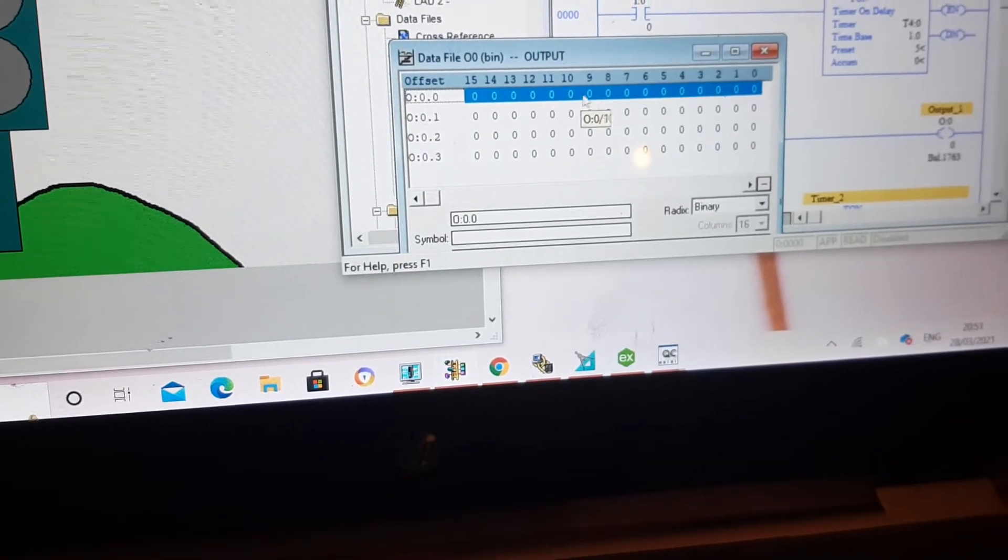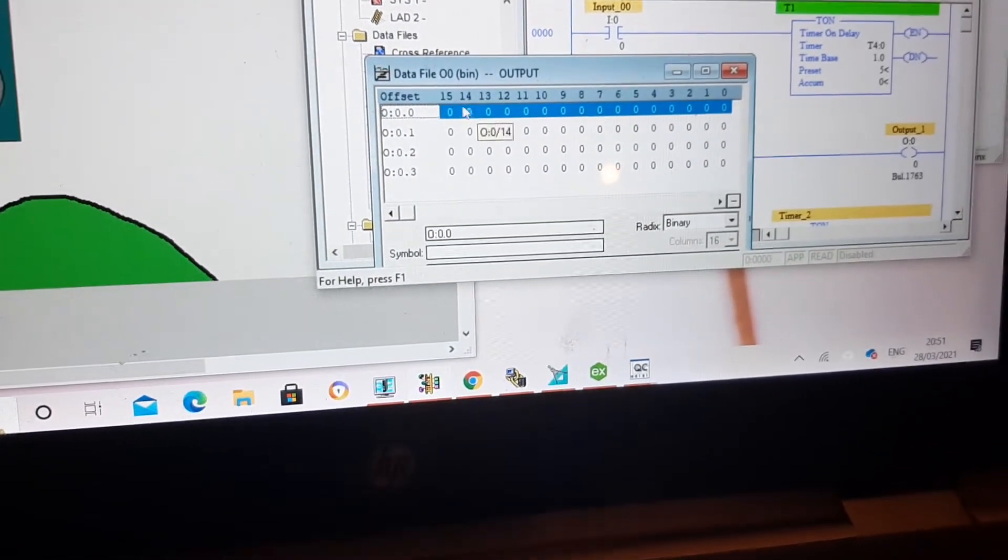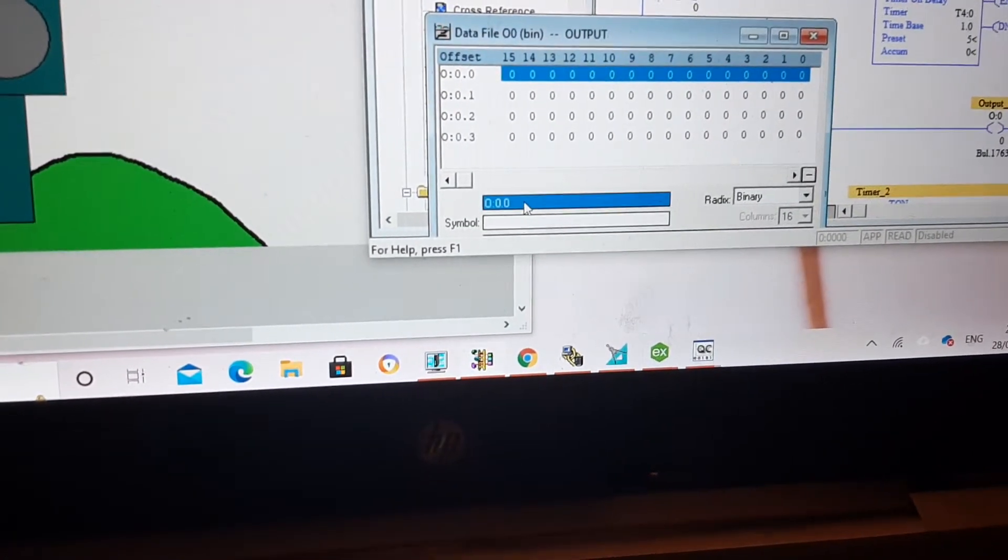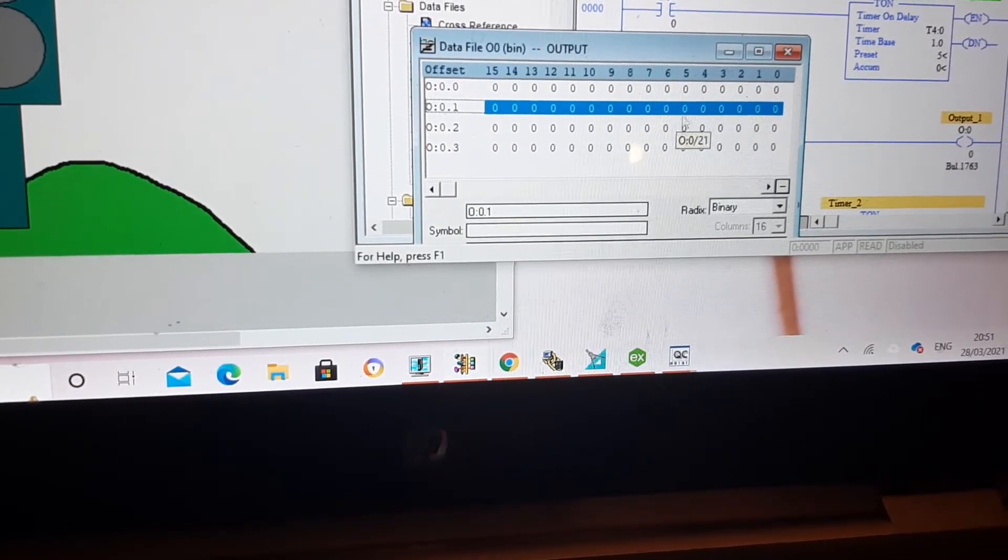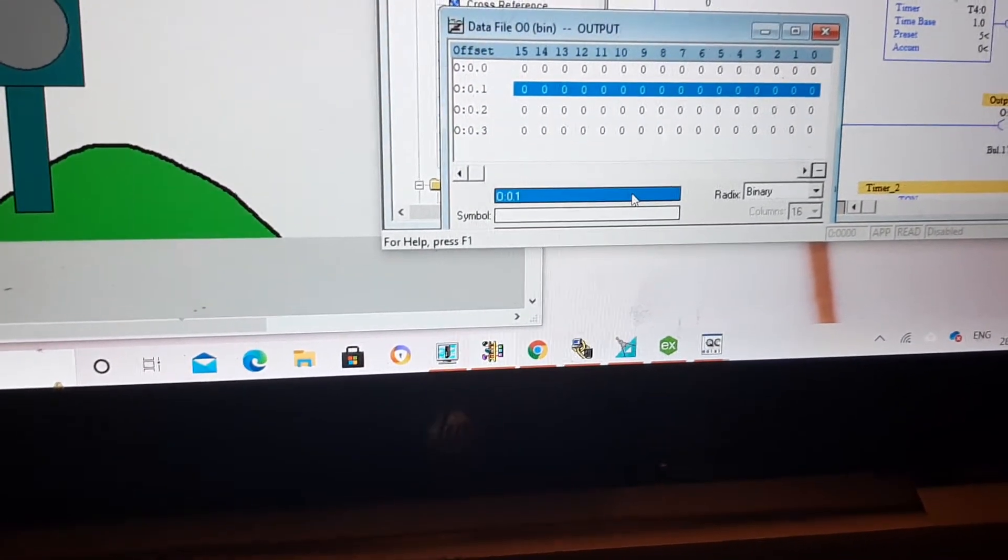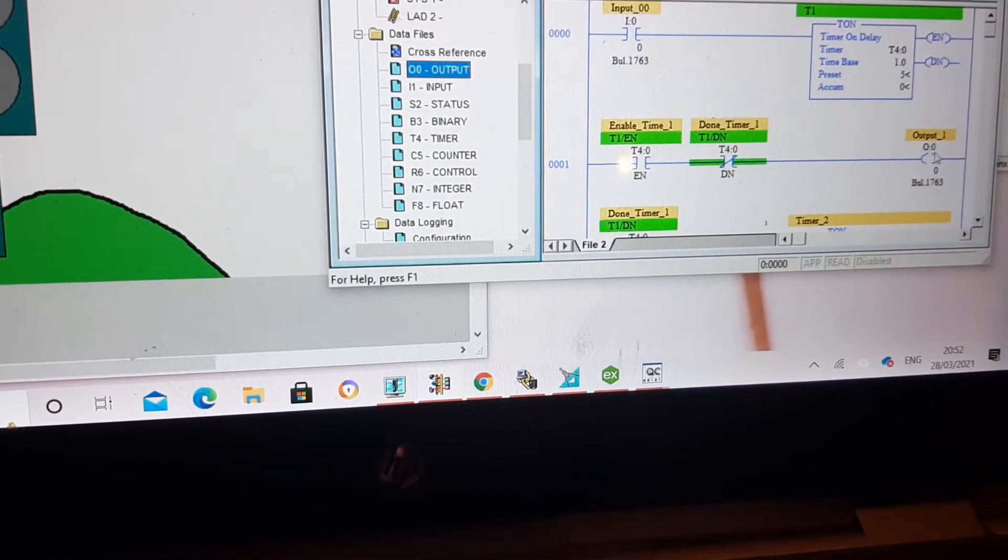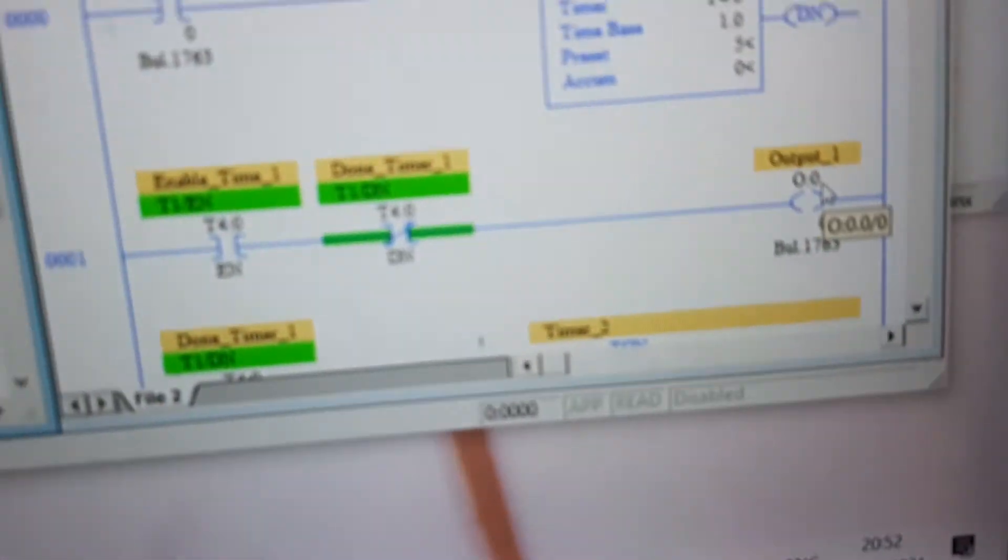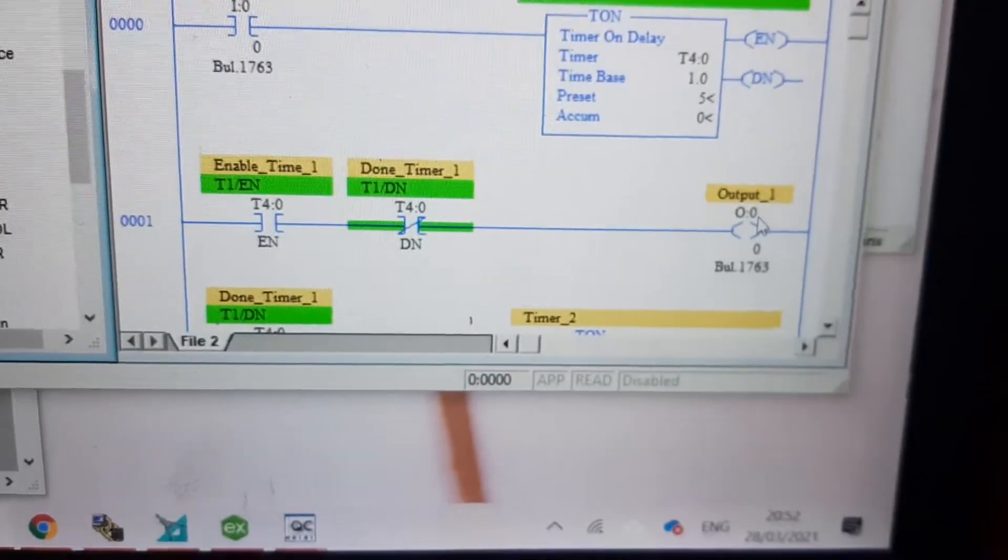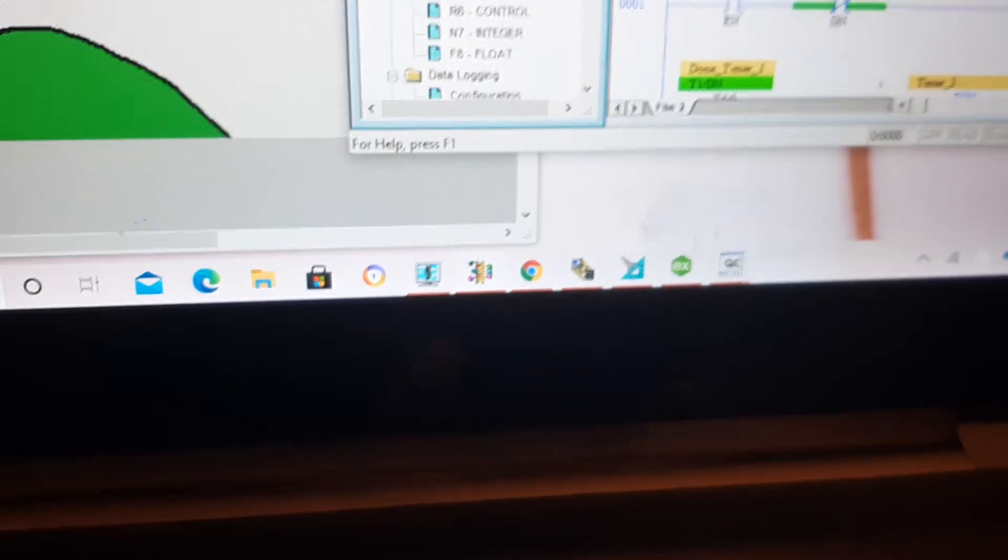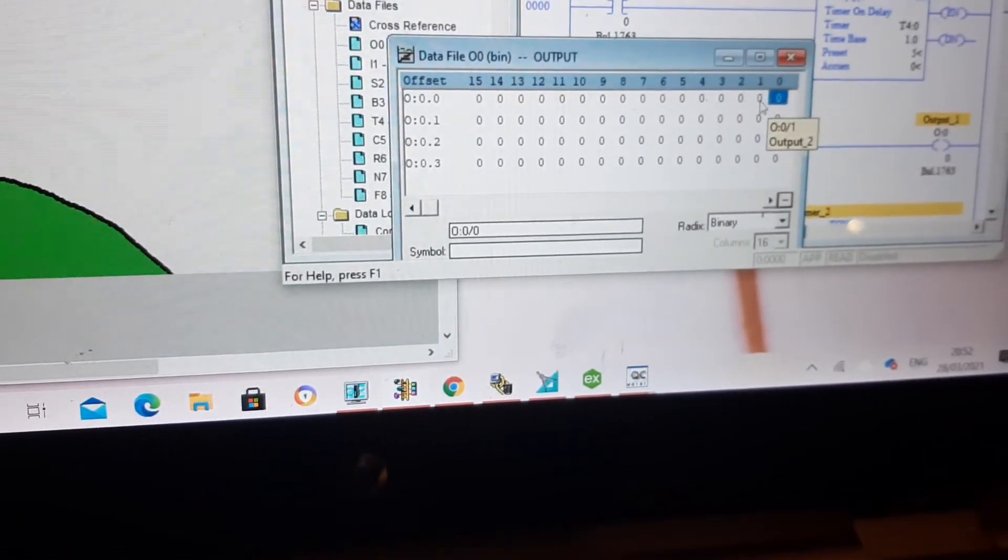So this entire part that is highlighted with blue color, that is going to have this address, and this entire line is going to have this address. So be careful of that. For example, here my output has address of, you can see it is 0:0/0, so I'm using the very first bit of my first byte.